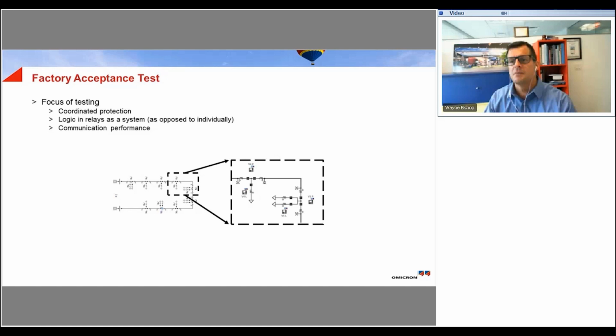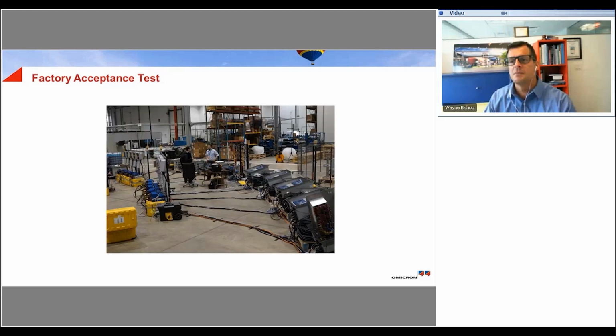For the factory acceptance test, or the lab test, we were fortunate enough to have the manufacturer of the switching solution invite us into the facility to perform the testing. We see here that we have multiple test sets set up, as well as all of the relays that would be used for the installation.